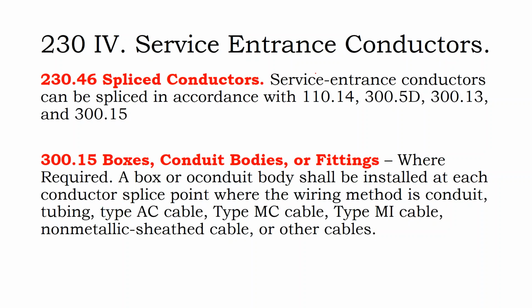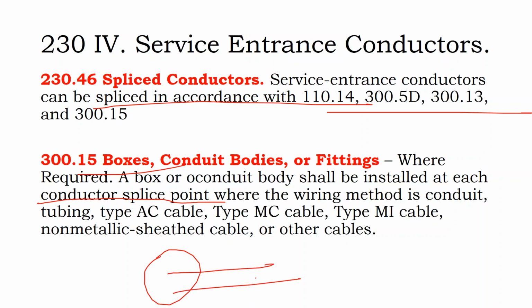Spliced conductors, service entrance conductors can be spliced and tapped according to certain rules. Conduit boxes and fittings should be installed at each conductor splice point. And so that shrink wrap tube that has a terminal for tapping a splice together, you know, that might not be a box or conduit fitting at your service entrance conductor splice point.